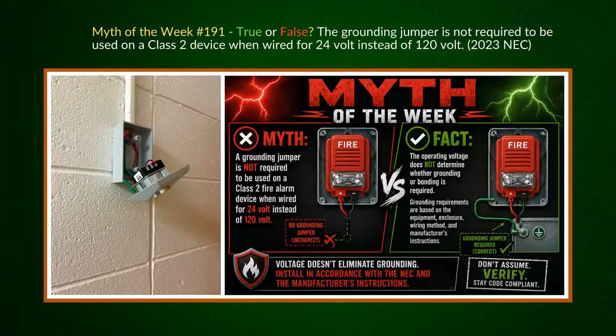So when you're looking at the myth, it was: a grounding jumper is not required on a Class 2 fire alarm device because it operates at 24 volts instead of 120 volts. That's why I write down here, and I'm looking at the little fire symbol at the bottom, I said voltage has nothing to do with this. Right. Okay. So I just wanted to point that out. So then I said, this is a fact: the operating voltage does not determine whether grounding or bonding is required. And then the National Electrical Code, what does it actually do? It bases all its requirements for grounding and bonding on what? The equipment, the enclosure, and the wiring method. And then also the manufacturer's installation instructions. It's based on that.